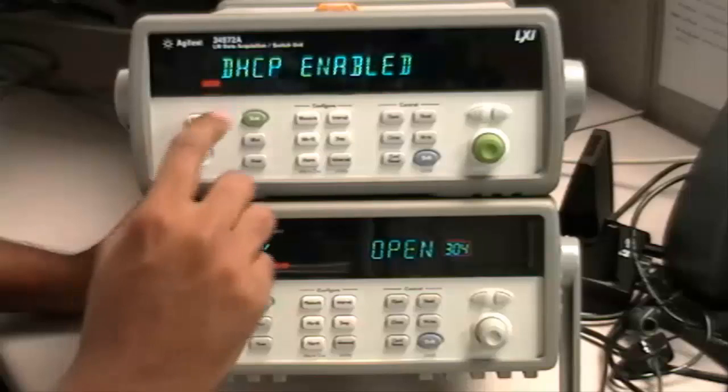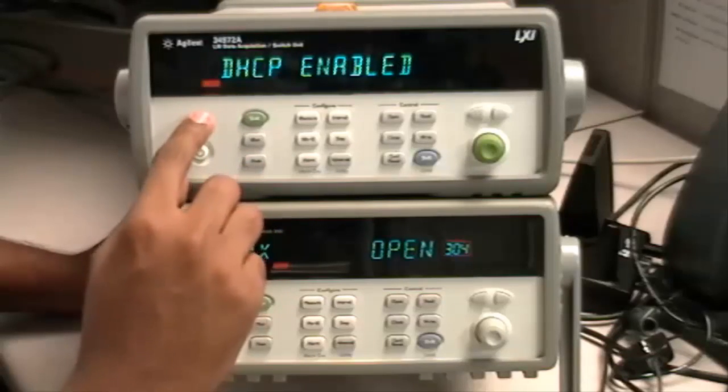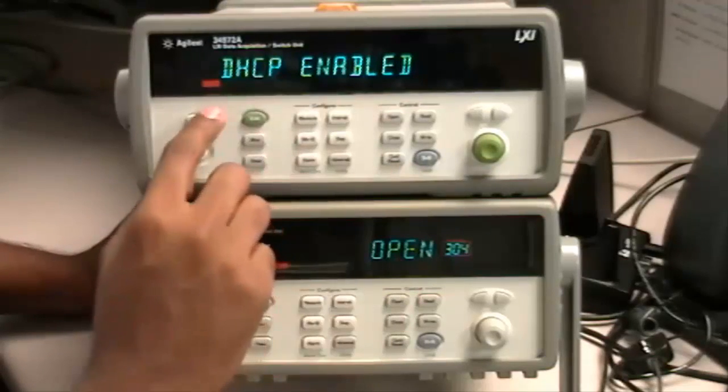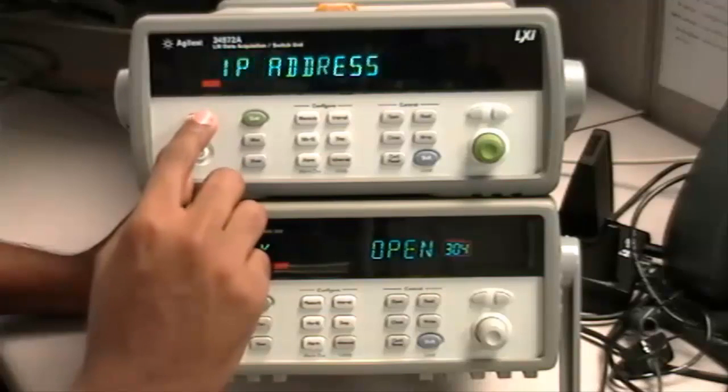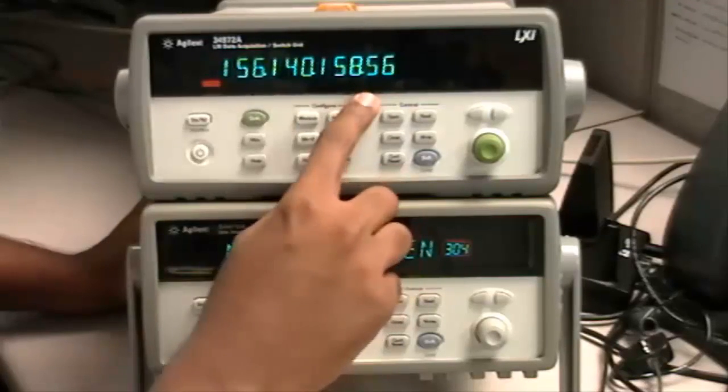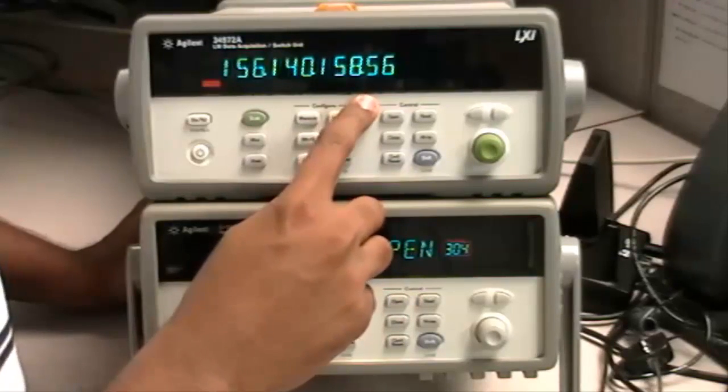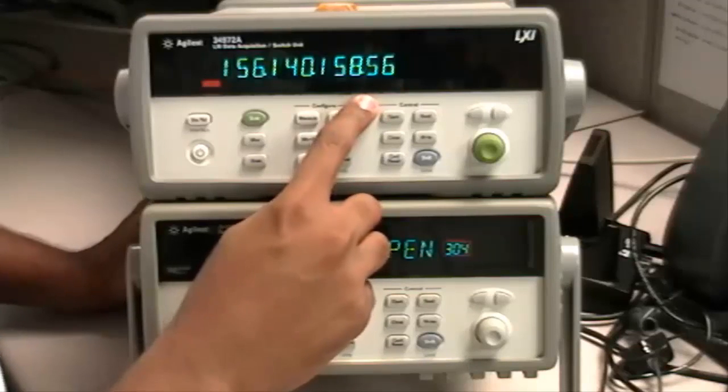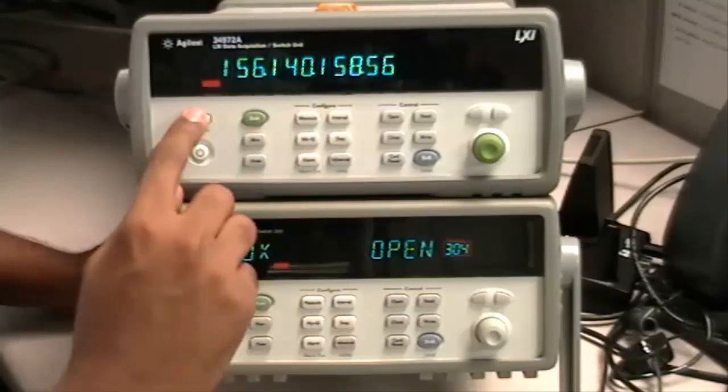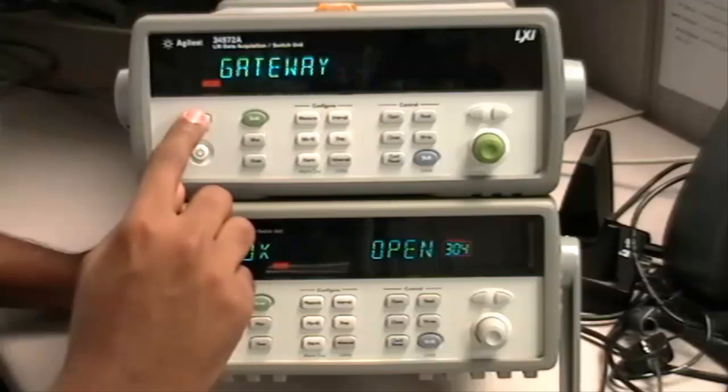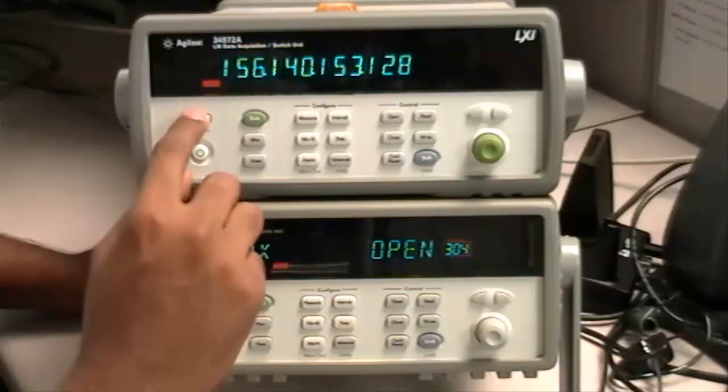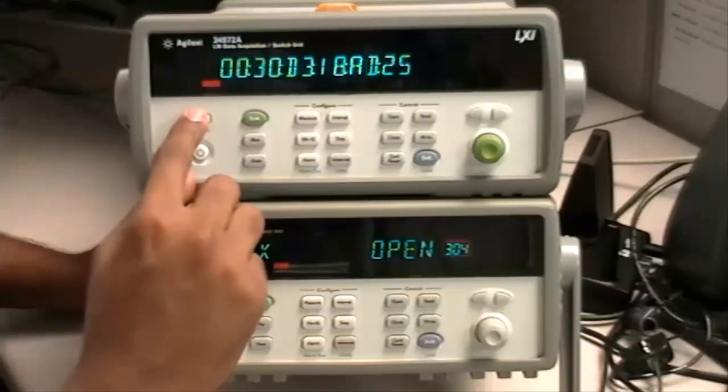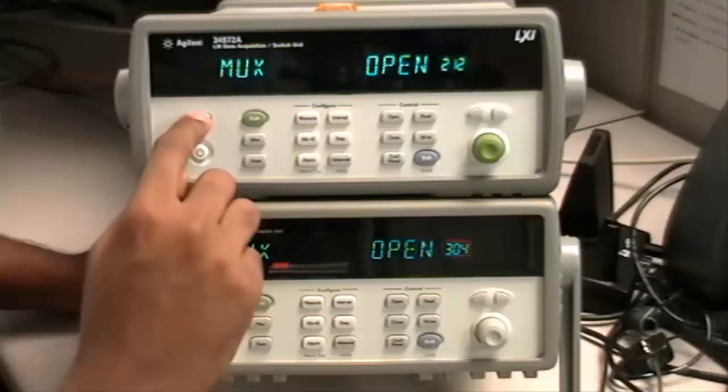Hit Store Recall. These are the other settings in the LAN interface. Take note of the IP address because that is what you're going to use in the Agilent IO Connection Expert. And then go through the other LAN settings by hitting Store Recall.